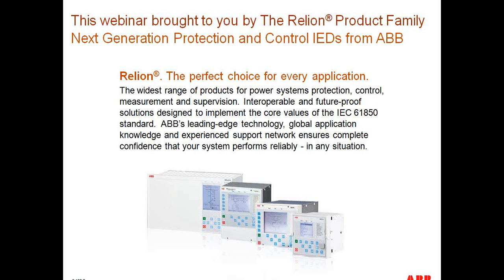At that point, this varies from manufacturer to manufacturer, but both of them provide bits or variables available that can in turn trigger a change of state on client-server. They can then close an output contact to go to an annunciator, or there are many other things that can be done. In the case of ABB relays, that information can be used to send a report to the substation gateway or to the HMI to inform that this disconnection has occurred.